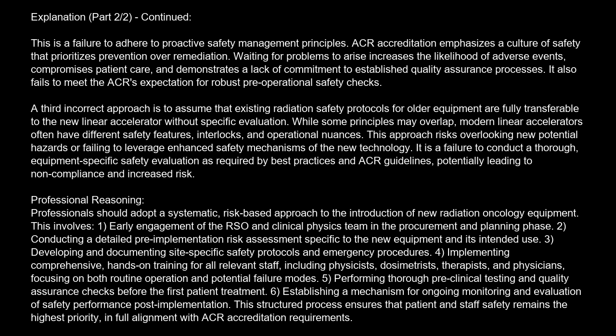It is a failure to conduct a thorough, equipment-specific safety evaluation as required by best practices and ACR guidelines, potentially leading to noncompliance and increased risk. Professional reasoning. Professionals should adopt a systematic, risk-based approach to the introduction of new radiation oncology equipment. This involves: 1. Early engagement of the RSO and clinical physics team in the procurement and planning phase. 2. Conducting a detailed pre-implementation risk assessment specific to the new equipment and its intended use.